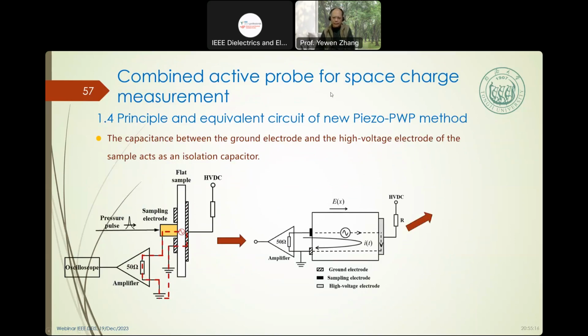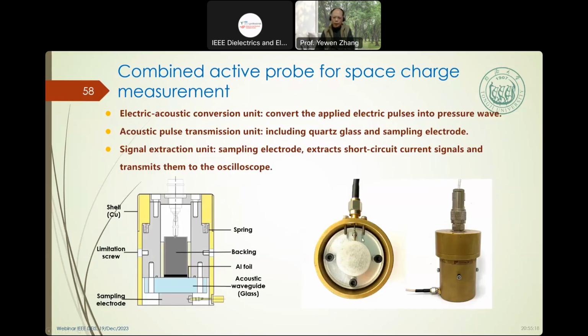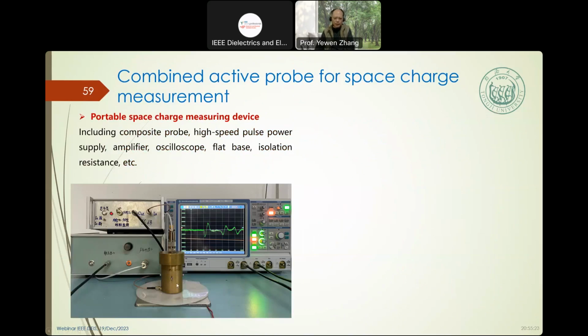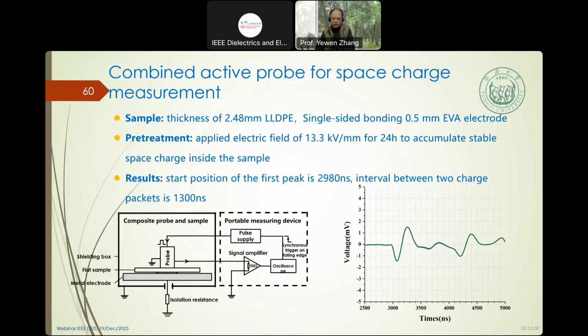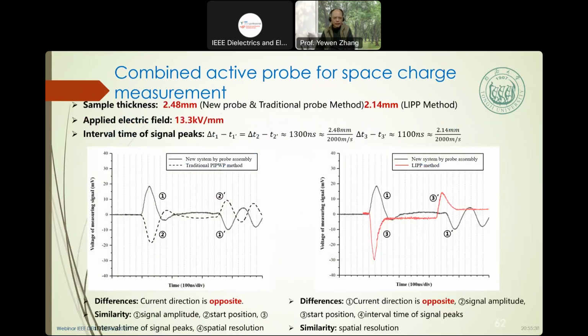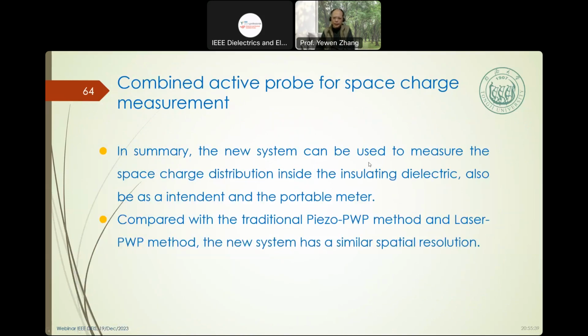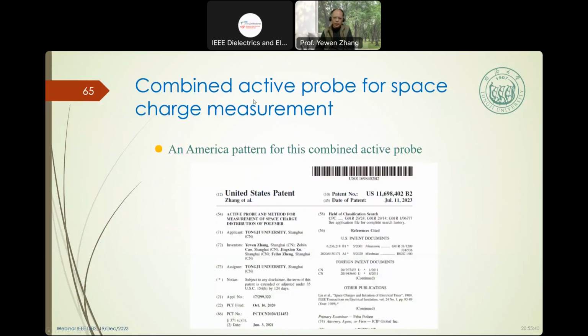I have a new result for the combination. We combine the samples. So we developed an active probe for measuring the space charge by the piezo, and using the compensation. This one is a probe. This is a probe for the space charge measurement. So the result is very similar to the laser. The combination is similar. The new system can measure the space charge distribution inside. Also, by combining with the traditional piezo, PWP or laser, the new system gives very similar results for the insulation. This one has an American patent this year.